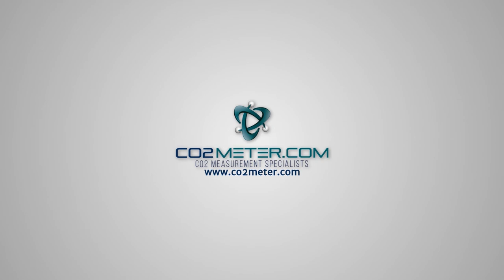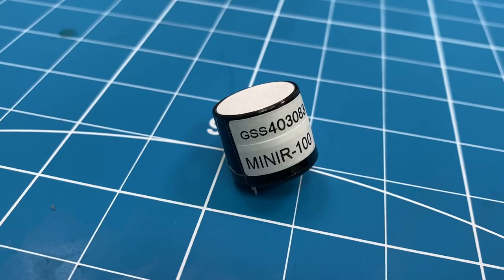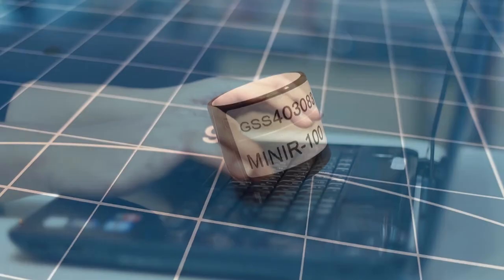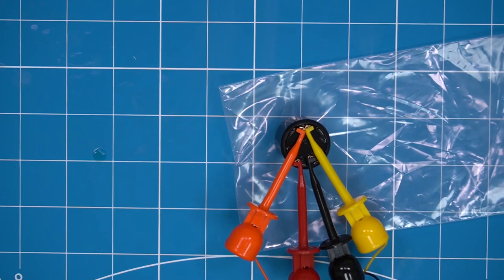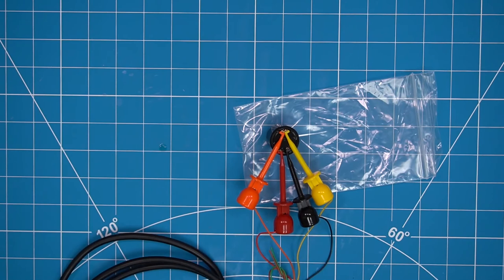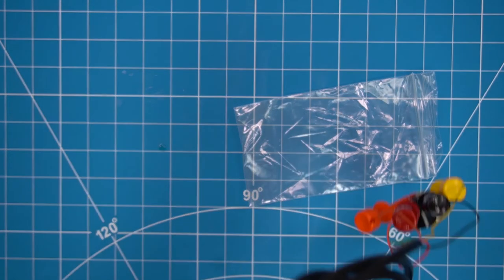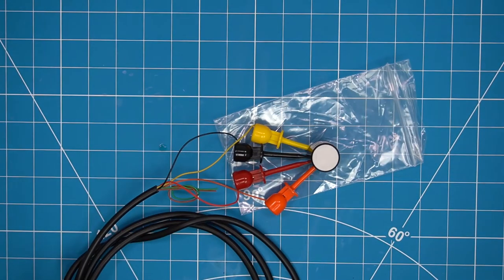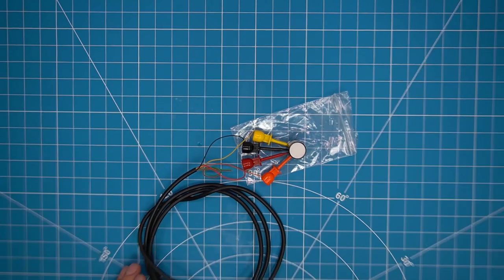We are the leading CO2 measurement specialist, and today I would like to give a demonstration on how to create a data log using a raw carbon dioxide sensor and a personal computer. This setup is a great way to create a data log with minimal costs and setup. This also demonstrates how to test a raw sensor without having to solder it onto a circuit board or integrate it into a system or device.